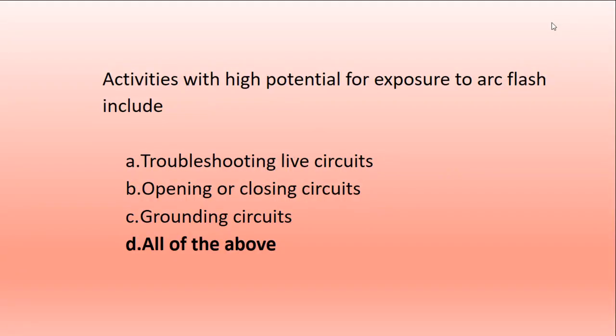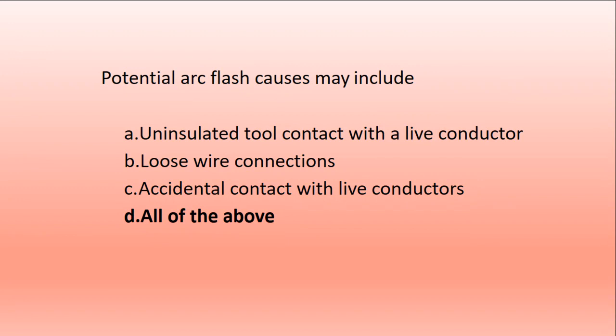Activities with high potential for exposure to arc flash include troubleshooting of live circuits, opening or closing circuits, and grounding circuits. These, options A to C, are all correct. Potential arc flash causes may include uninsulated tool contact with a live conductor, loose wire connections, and accidental contact with live conductors.